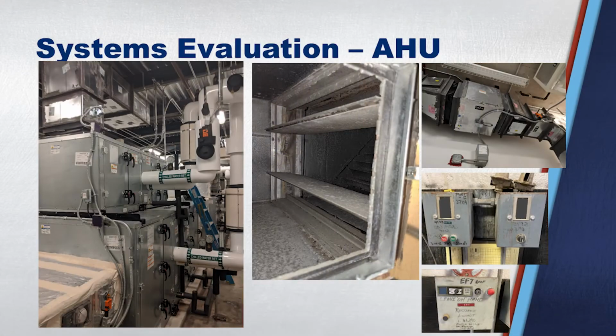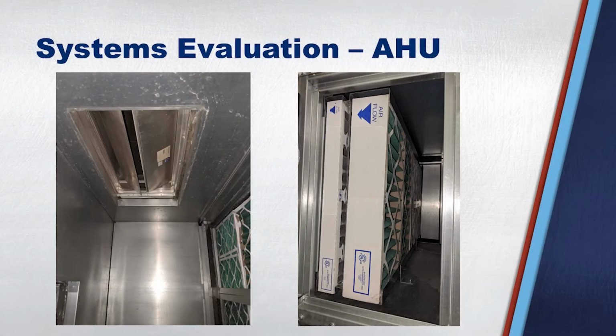So this is the actual units where they had the outside air coil on top, the return coil on the bottom, and we went out and started to look at this unit. So you can see a picture of the outside air dampers. They don't look that bad. They were open, so it correlated with the BAS. Some of their units had little outside air fans that you can see on the top right. And then the exhaust fans, because we're evaluating a system, not just an air handling unit. And the note on the bottom one, I think it says, leave run all the time. Well, guess what? When you turn the unit off, you're going to have a negative building, other issues, something you might want to point out.